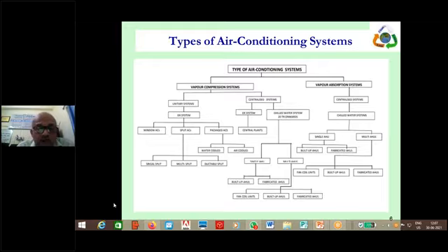So it is a vast field, whereby firstly you must start with the heat load calculation. How much is the heat load? And first, before that, you must know what are the conditions to be maintained and what are the other loads: solar load, equipment load, then occupancy load. All these things are done in heat load calculations. Softwares are available. Manually also, people like me, I do mostly manually. So manually, we can then finalize that tonnage required. We can finalize the air handling units, air capacity, humidified air capacity. We can finalize pipe sizing. We can finalize other basic things. Then later on, when we go for equipment selection, then according to the TR and other things, equipment are selected.